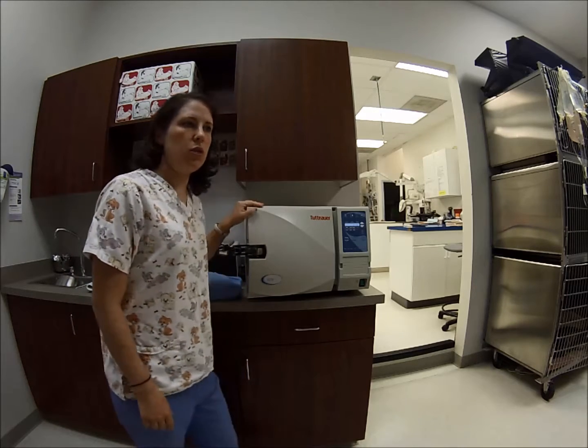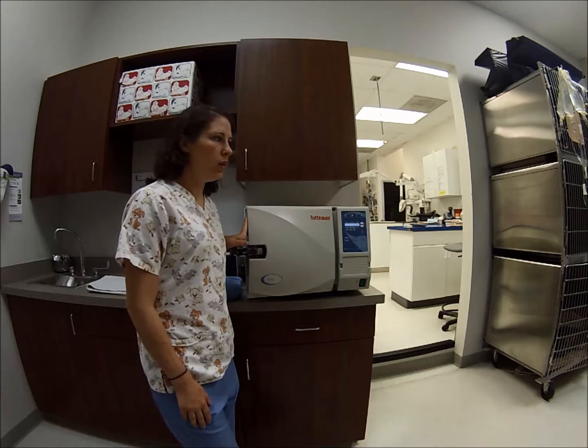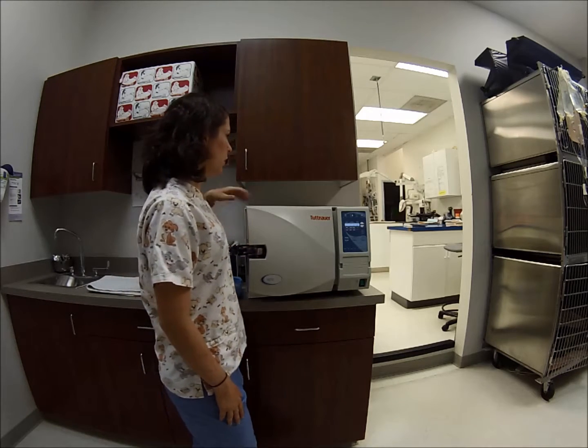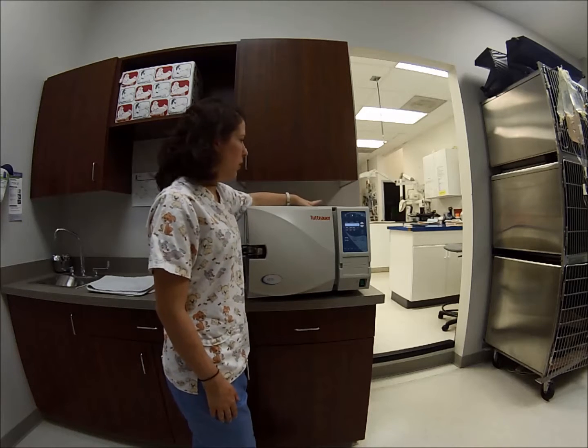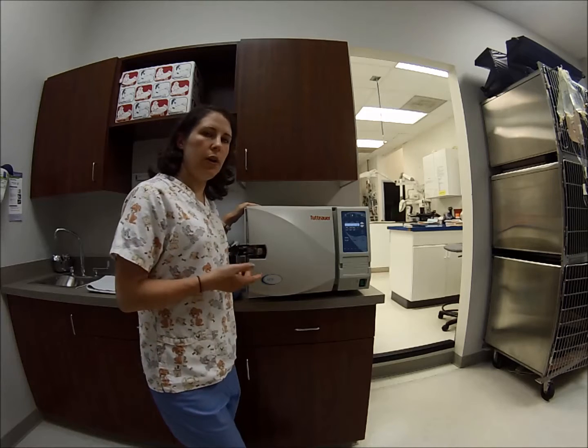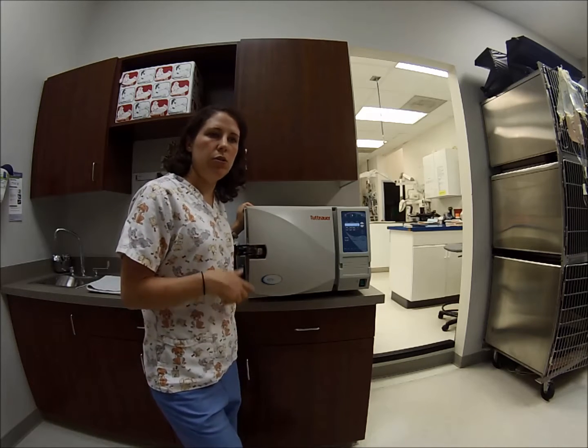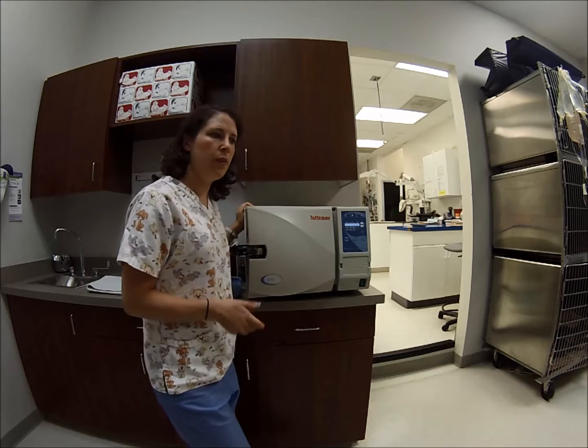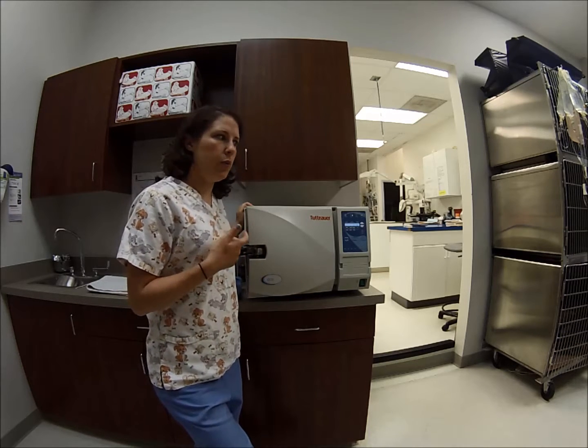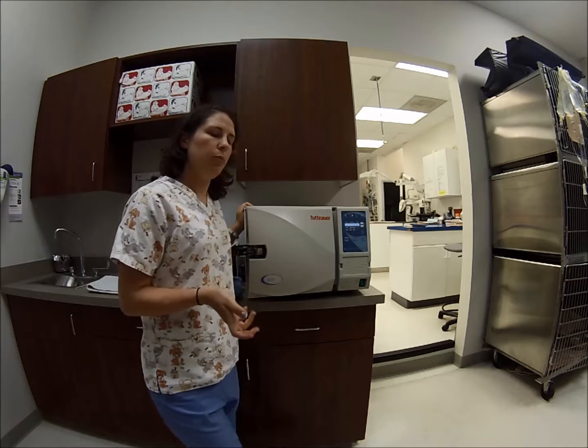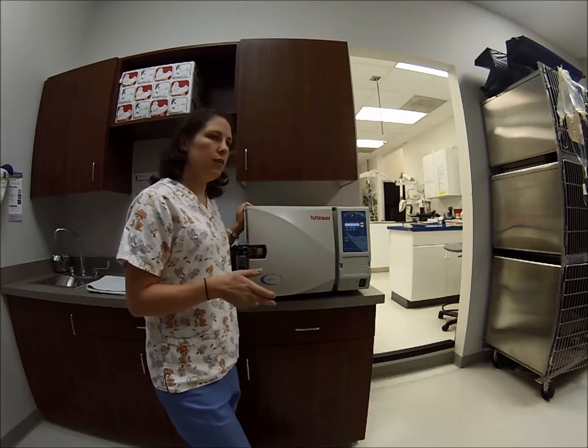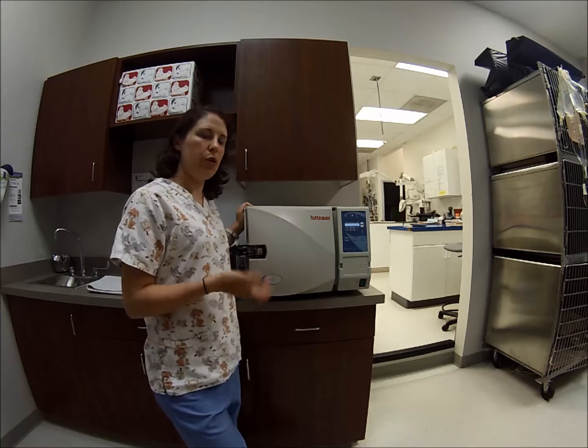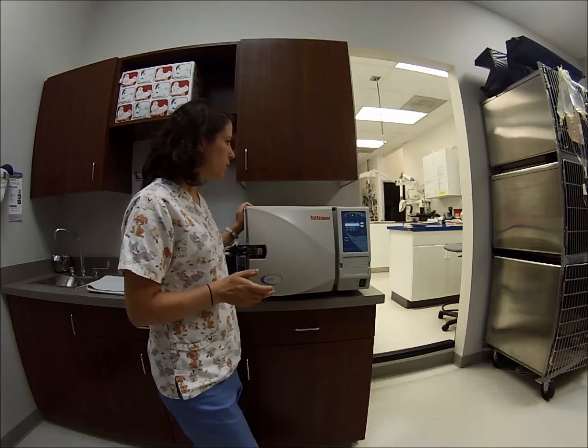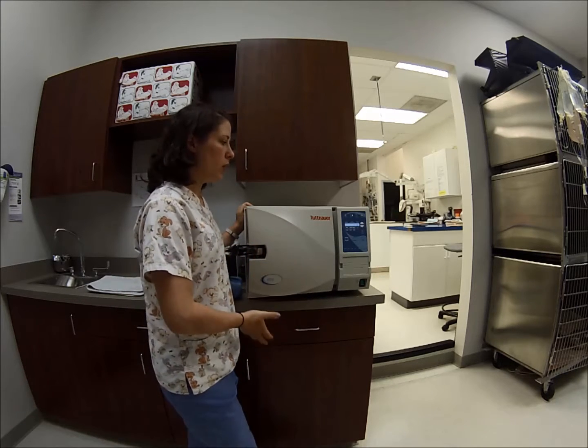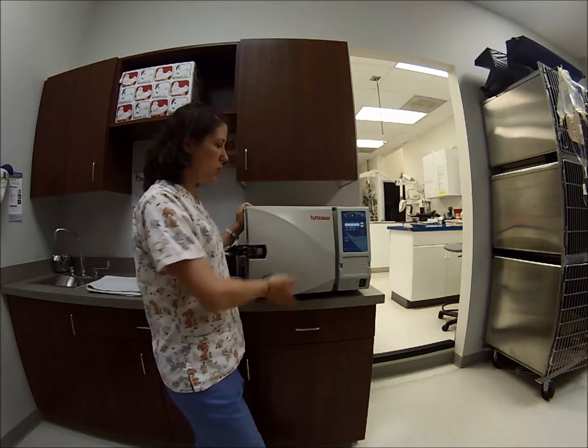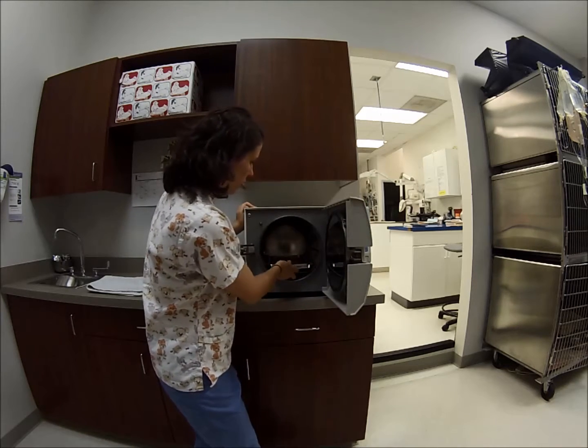So, autoclaves use steam under pressure to kill microorganisms. What happens is we load the machine with distilled water in the water port. The water is heated up electronically to a temperature of about 270 degrees Fahrenheit. Once the water is heated up, it will be turned to steam, and the steam will push out any extra air. And when the air is gone, there'll be a buildup of pressure. So the pressure builds up to about 27 psi. And then the steam is used to clean and sterilize the packs, penetrating upwards through this tray here.